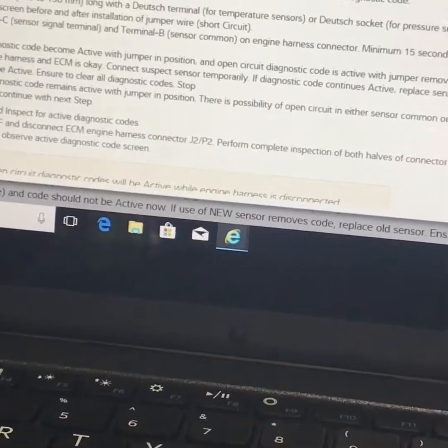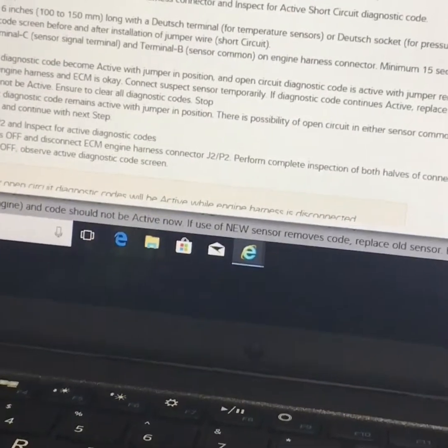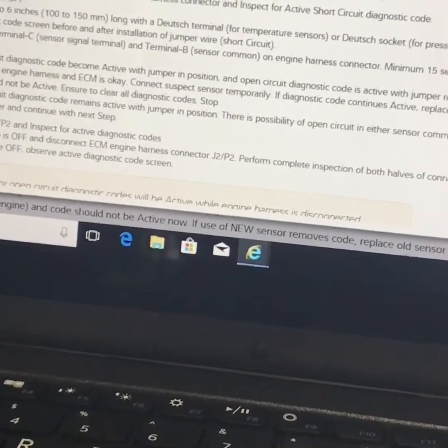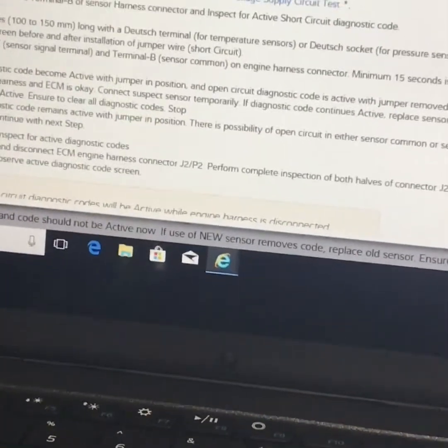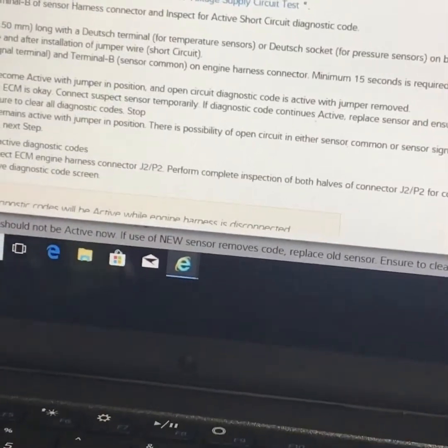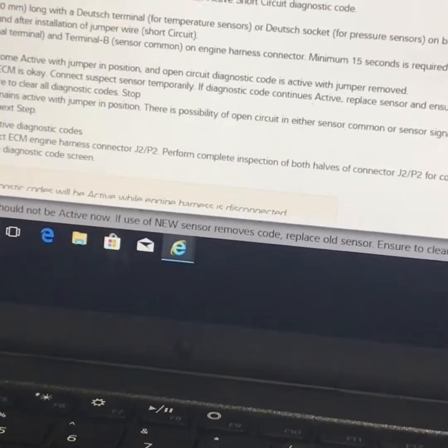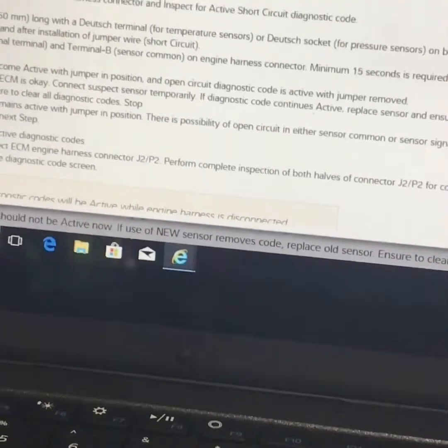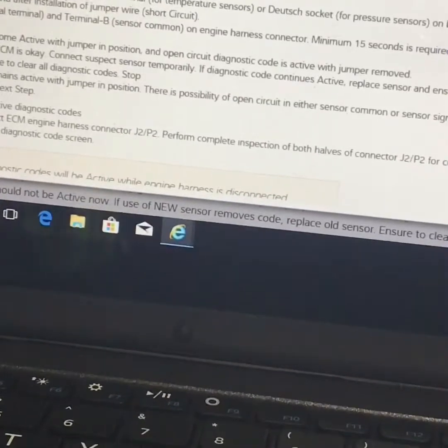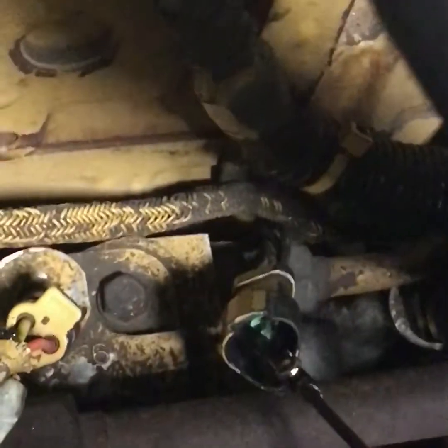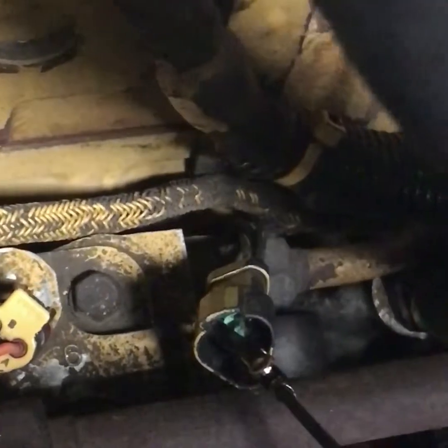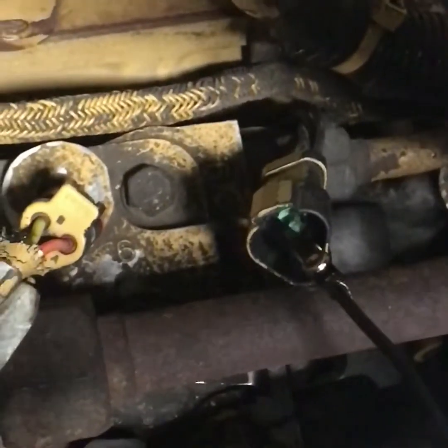Since we know our sensor supply voltage is correct, our next step is to short the sensor from terminal C to terminal B. After we short the sensor, we're going to look for a change in our code - from a 108.3 code to a 108.4 code, indicating the code went from an open to a short. As you can see, we have our sensor shorted from terminal C to terminal B.